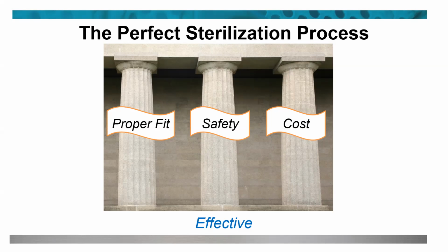First thing that you want to do to get started with this is look at all of your inventory that needs to be processed in low temperature sterilization, and look at the manufacturer's recommendations. The manufacturer's recommendations change sometimes because there are new sterilization modalities and cycles that come available. And so you want to check to make sure that you have the most current recommendations for that.